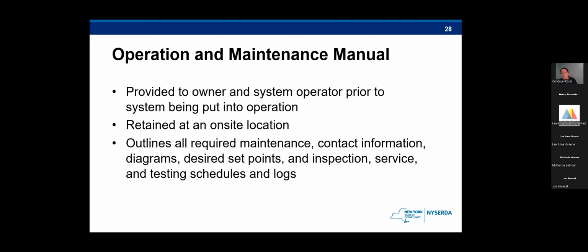So the operation and maintenance manual must clearly identify the required routine maintenance actions, include the contact information of the agency that is contracted to service the system, and provide the maintenance and calibration information, including wiring diagrams, control diagrams, and system programming instructions. It needs to outline desired control set points. It needs to provide a schedule for inspecting and recalibrating all controls. It also needs to have a service record log, and basically have all the inspection and testing records maintained in this manual.